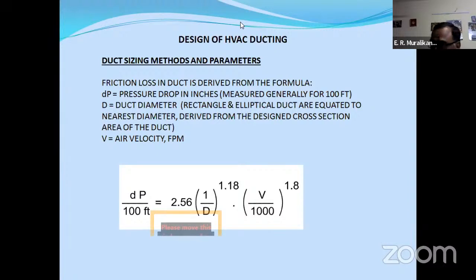Some people may ask what is the difference between rectangle duct and round duct, how much friction loss there could be. There is a separate formula for round and rectangle also, but we are not going in depth in this because it's a separate topic. When you go for round duct, we generally not only take the velocity of the air, we also take into account the weight of the dust particle when you're talking about scrubbers and powder handling systems. So there, this formula gets corrected in some other way. The dust particles are also captured by the velocity or vacuum pull created by the fan. So we are not talking about that here. That is a special application.